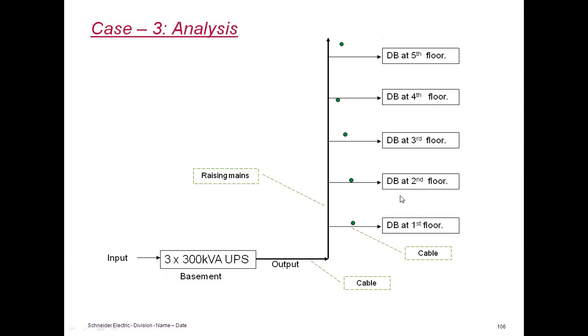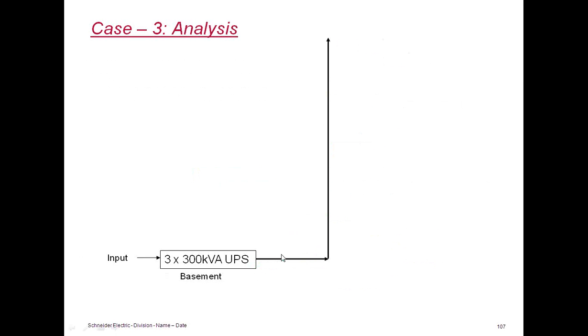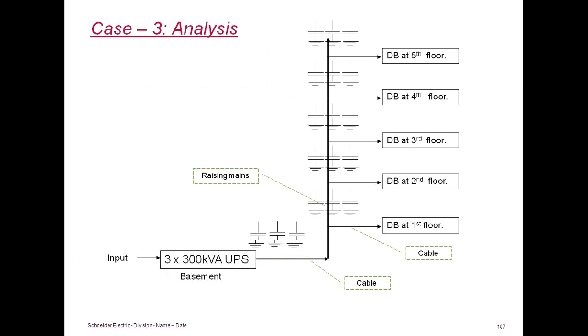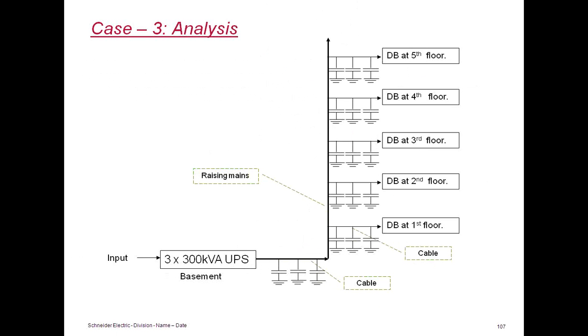Harmonics from the distribution boards on each floor are coming out, going to the rising mains and going back to the UPS on the main power cable. But because of the cable, the cable capacitance was adding in between, and a very small amount of leakage current coming from this cable capacitance goes to the common ground system. We had an earth leakage breaker at the output of the UPS in the basement, and it is adding up at the ground and just shooting into the ELCB and tripping the breaker. Whenever this floor is switched on, the leakage current is about 34 milliamperes. Whenever this floor is switched off, with all the 4 floors on, the leakage is about 26 milliamperes. So that means the difference. So this building was having tripping at least once in a month. That is huge revenue loss for the customer, just because of harmonics flowing into the cable capacitance.